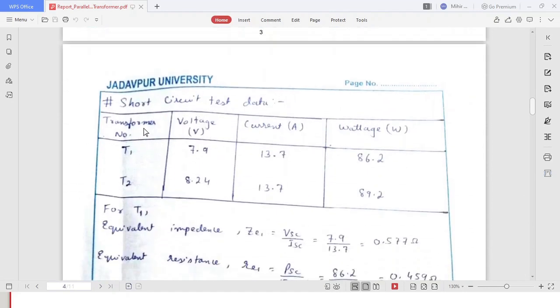Now these are the short circuit data which was collected from the laboratory. This T1 voltage is 7.9, current 13.7. 13.7 is the rated current of the transformer. You know that short circuit is performed under the rated current. So this is 13.7. These two are same, 13.